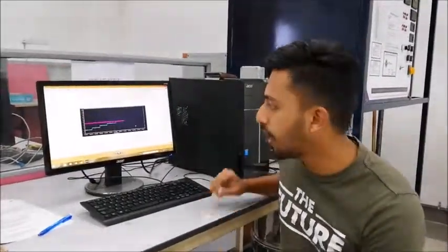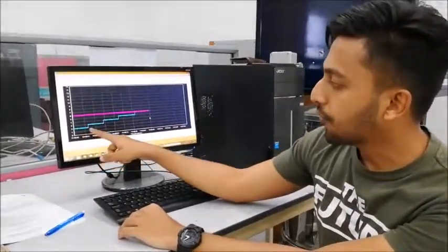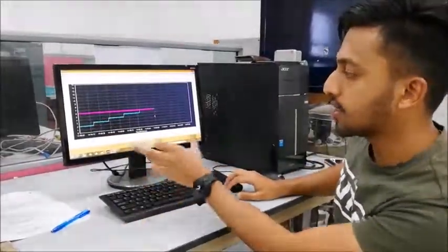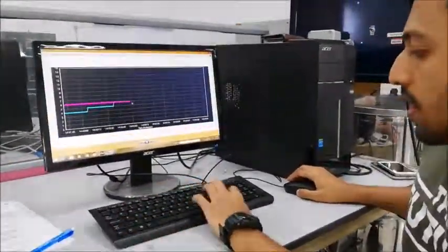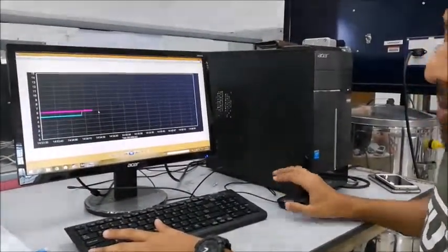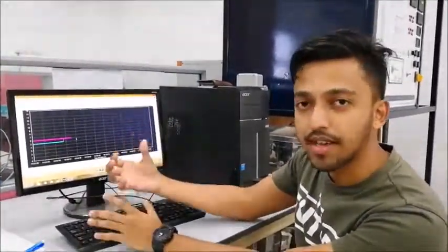This is the result that we got using the DAQ software. As we can see here, when the proportional is 2, the time taken to reach the desired setpoint of 6 is longer compared to when the proportional is 4 and also when the proportional is 5. This means that when the proportional is increased, the time taken to reach our desired level of 6 is faster compared to when it is low.